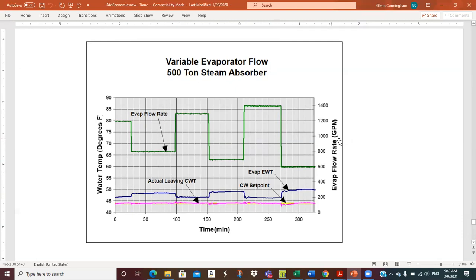So you can see what they've done here. So we start over here. Here's our flow rate over here. There's 1200, 1400 GPM all the way down to 600 GPM. And so we're starting over here at 1200, and then we take a step change down to 800. And you can see the actual leaving chill water temperature through all of this doesn't vary very much. I mean, it's pretty darn good control. And so then you can see your return water temperature shows more of an impact than your leaving water temperature. And so they're just doing these step changes and looking to see how that leaving water temperature varies. And the biggest one, we go from 1400 down to 600. Wow, so that's like a 60% reduction.